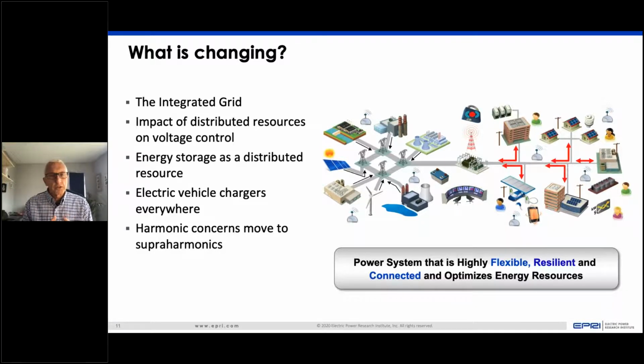We've done a pretty good job of making these devices better in terms of harmonic generation. To do that, we've used technologies like pulse width modulation that move some of these concerns up to higher frequency harmonics—we call those supraharmonics, in the range of 2 to 150 kilohertz. We'll take a look at the importance of these higher frequency harmonics as we go forward.